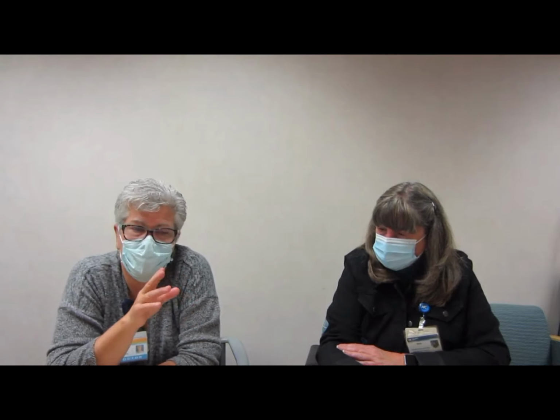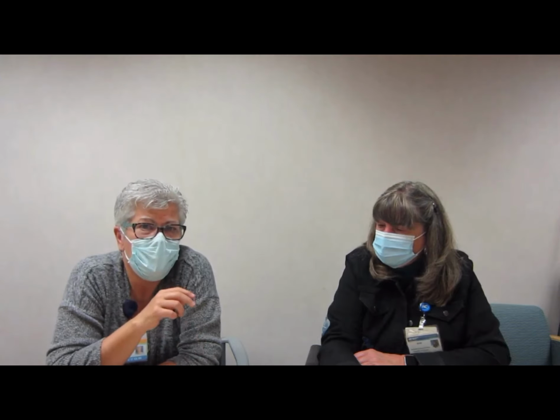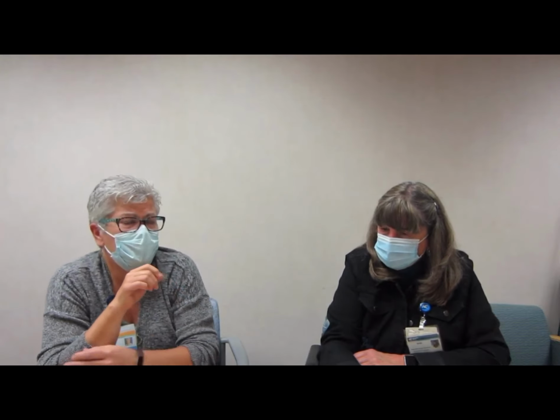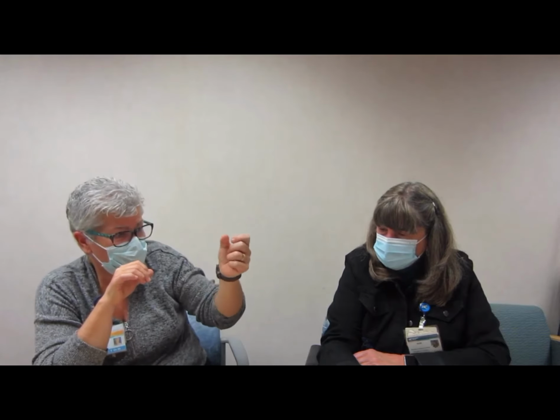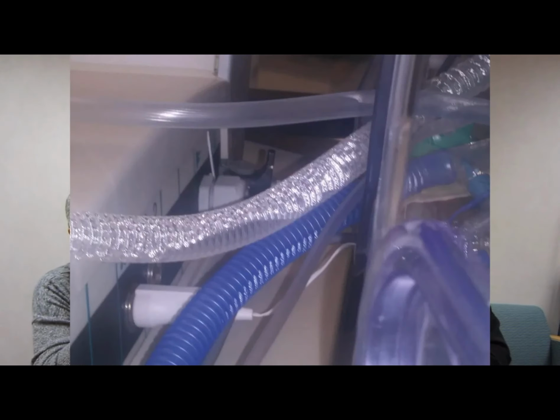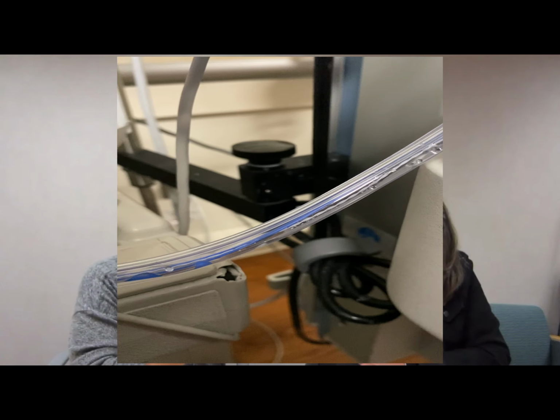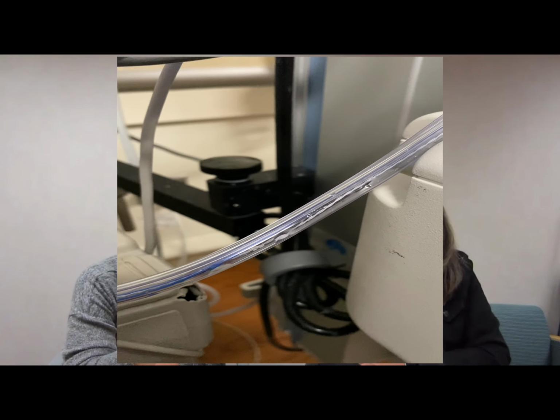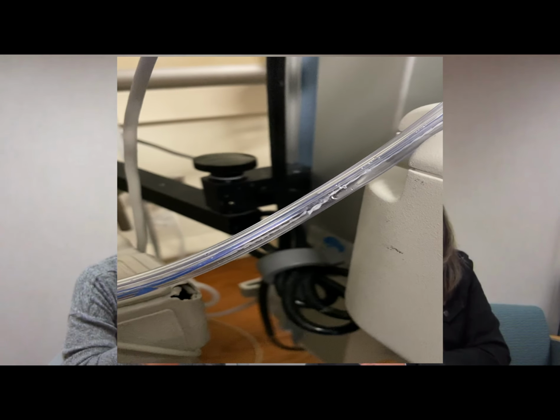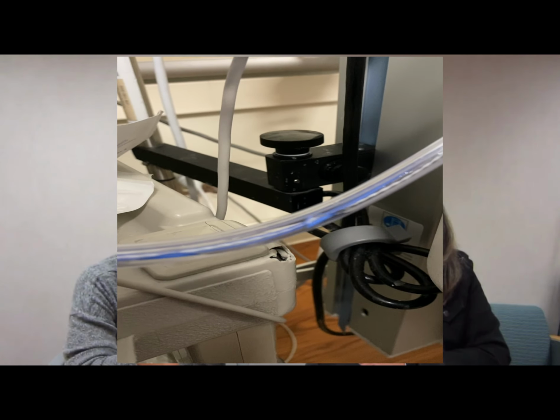We just had a baby who had a tubing full of water. Once we got rid of it, the baby started jetting much better, and the oxygen requirement went down. So it is a mechanical issue, and you have to keep your eye on it. When you have a baby on the conventional vent as well, if you have a lot of the tubing outside of the vent, water collects in the bends of the tubing. That oscillation of the water going back and forth can sometimes trigger the vent to give a breath to the baby. So make sure that water is out of your tubing several times a day.